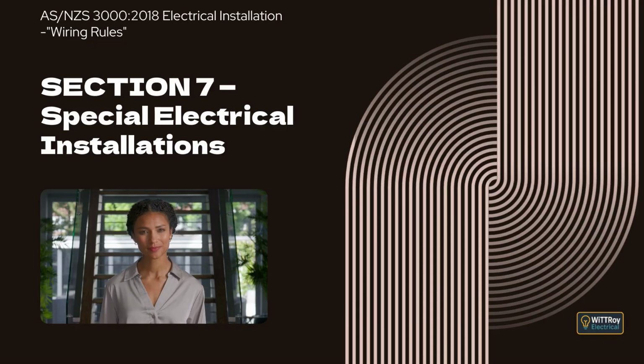Clause 7.2.9.1, general. This clause explains that in New Zealand, lifts required to operate for firefighting or other emergency purposes are safety services and must comply with the requirements of this section. Clause 7.2.9.2, control and protection. This clause explains that each emergency lift, or group of emergency lifts, must be controlled and protected independently of all other lifts. It explains that main switches controlling lifts must be arranged in accordance with Clause 7.2.4 and clearly identified so they are distinguishable from switches controlling other lifts.